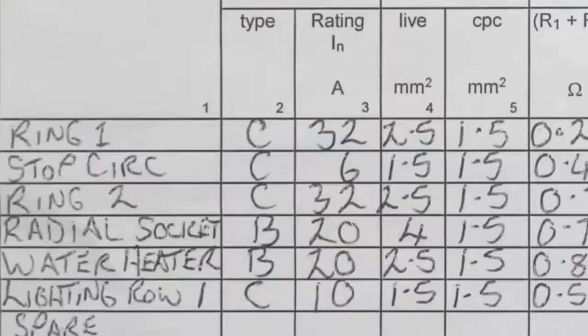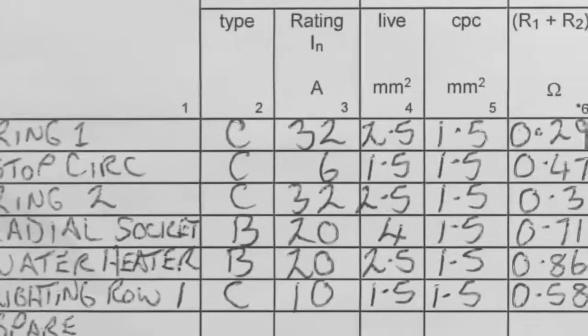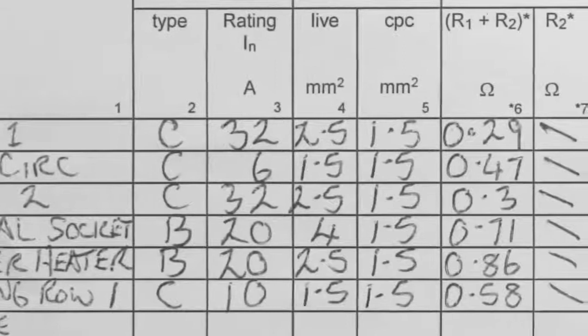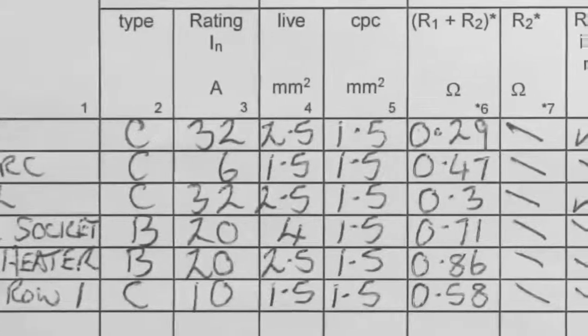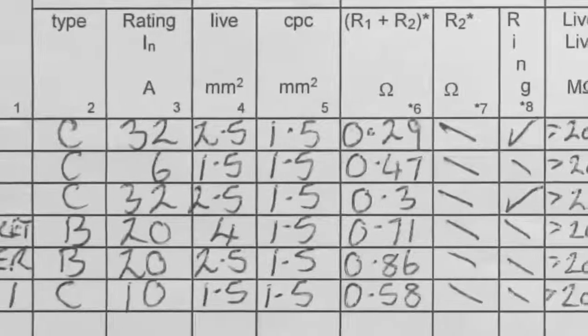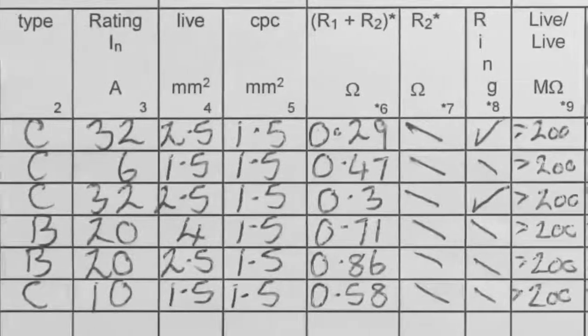Now, for instance, on this certificate here I've got various circuits and if we take circuit 4 we've got a 20 amp circuit wired in 4mm with a 1.5 CPC and we've got an R1 and R2 value of 0.71. That's all the information I need to calculate the volt drop in that circuit. So for a first instance we can use R1 and R2.